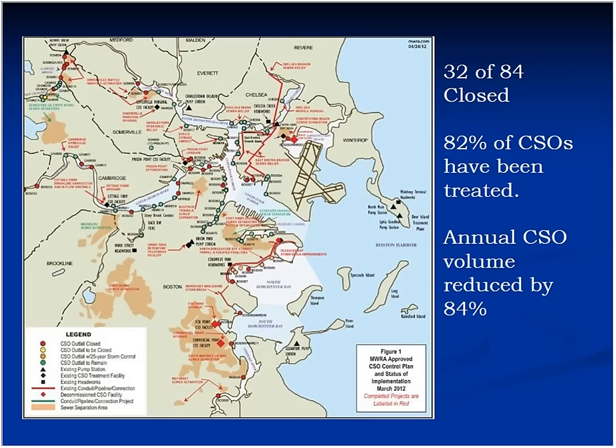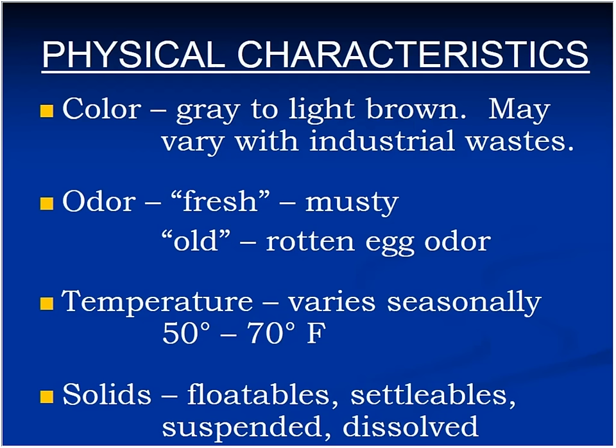Increasingly, these are being addressed. This shows Boston, how many they had, and they've reduced them. They've closed 32 out of 84, at least at the time of this slide. So they've reduced quite a bit. A lot of them are being designed so that they actually have some amount of treatment. They'll remove grit and solids, and they'll also disinfect. So you're not maybe putting clean water out there, but at least you're taking care of the pathogens.